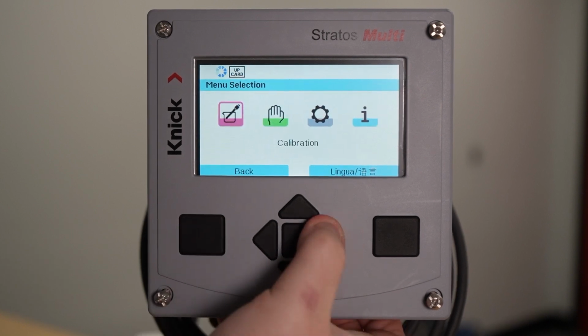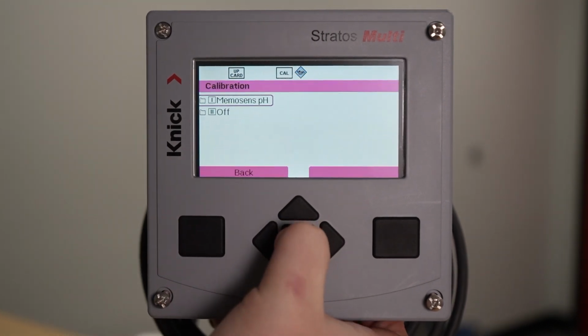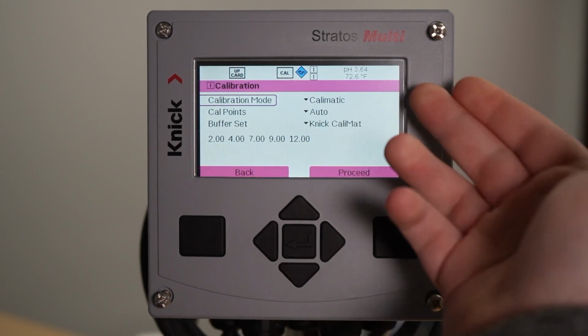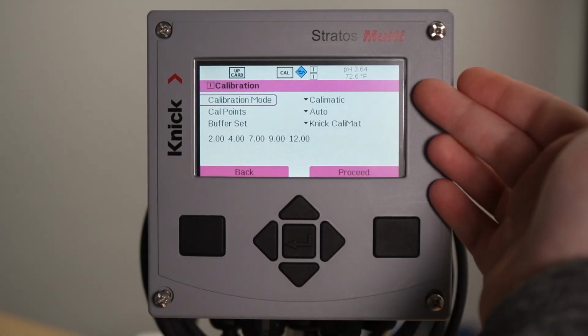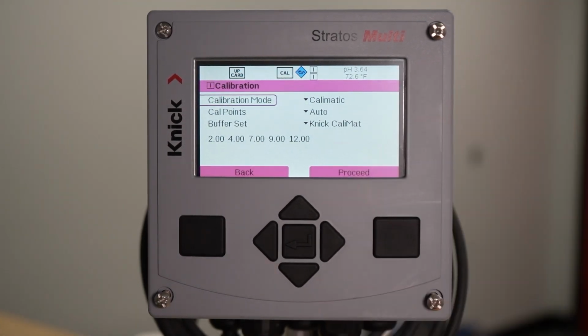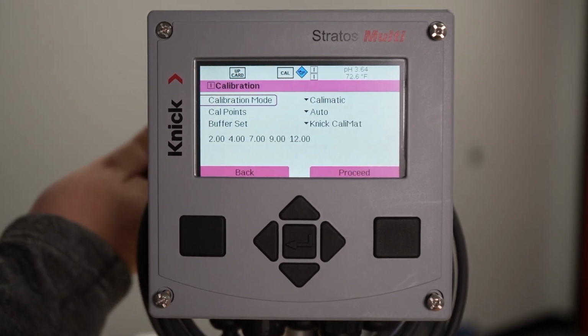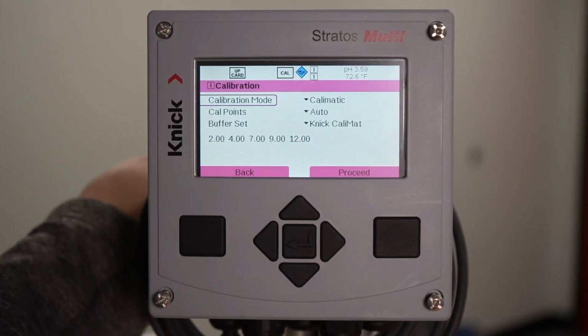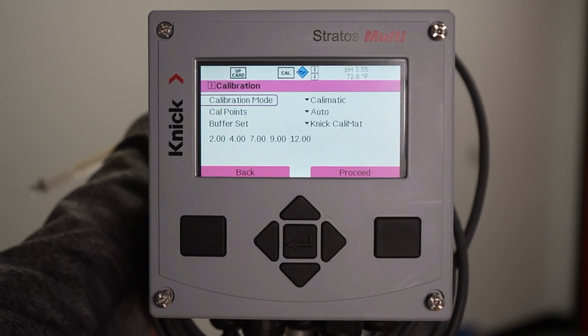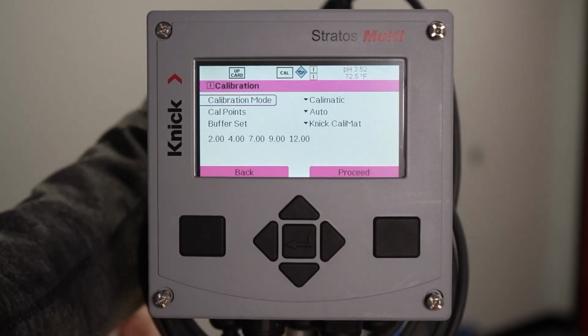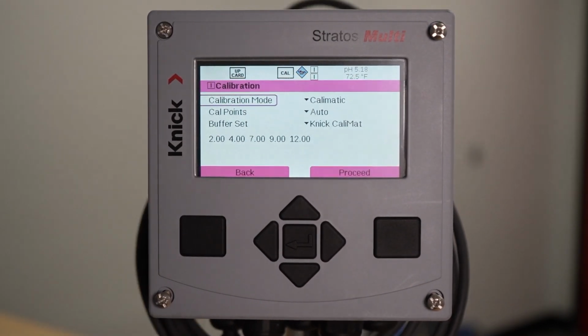If I go into Menu, then I go to Calibration, MemoSense pH, up here in the top right-hand corner, I now have readouts that show the active pH readings of the sensor. So I don't have to guess if the readings have stabilized before I put it into a new buffer. The calibration hasn't started, but if I throw it in this 7, you'll see in the top right-hand corner, the pH slowly creeps up. So you could wait and actually know when your device has a stable reading, and then you can proceed into your calibration.